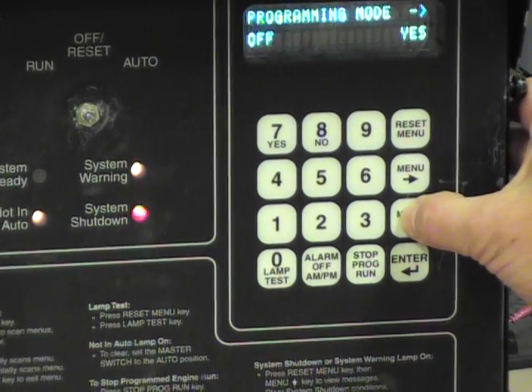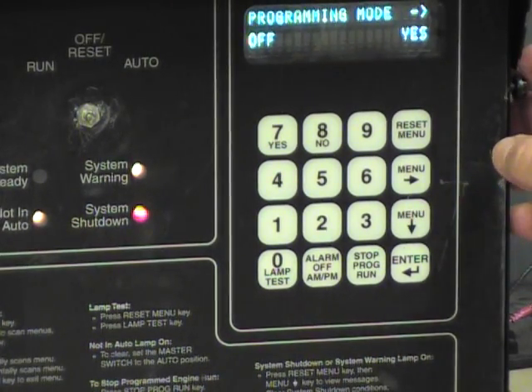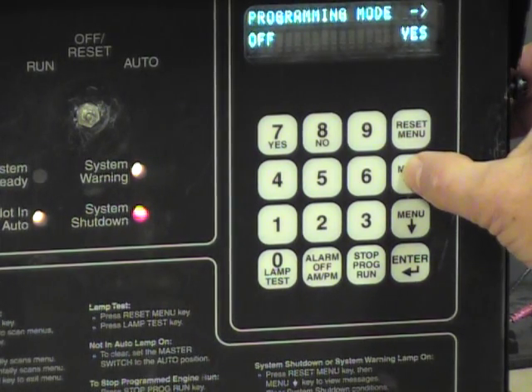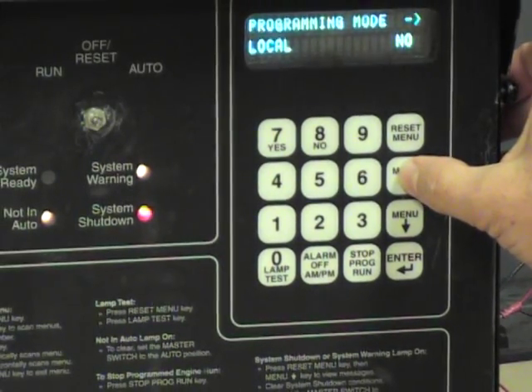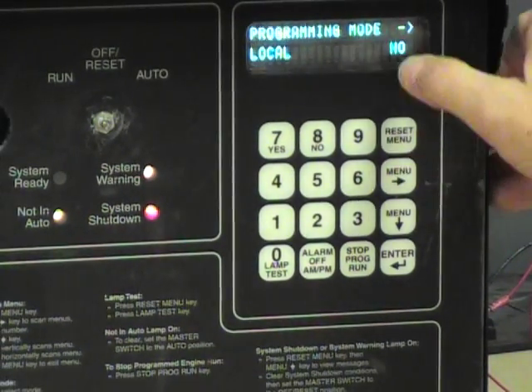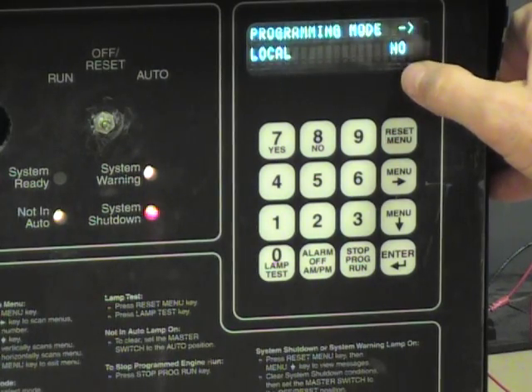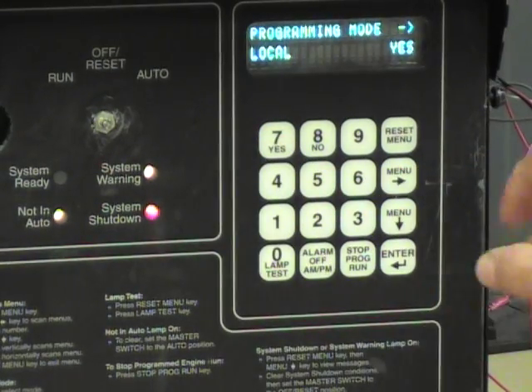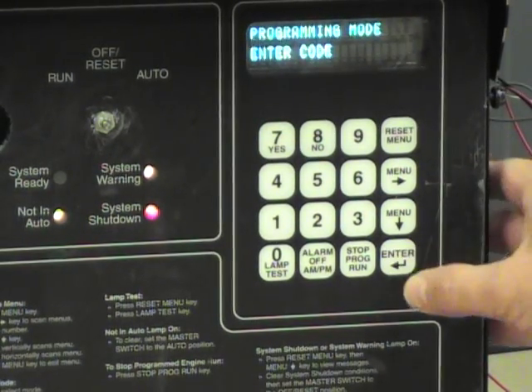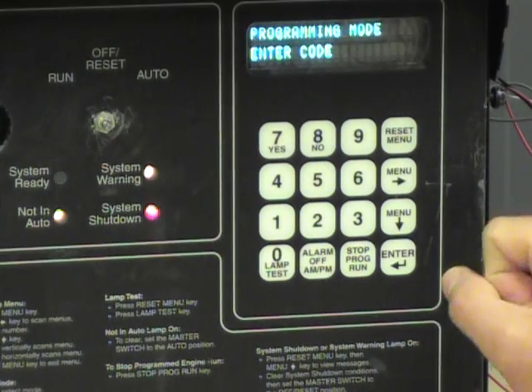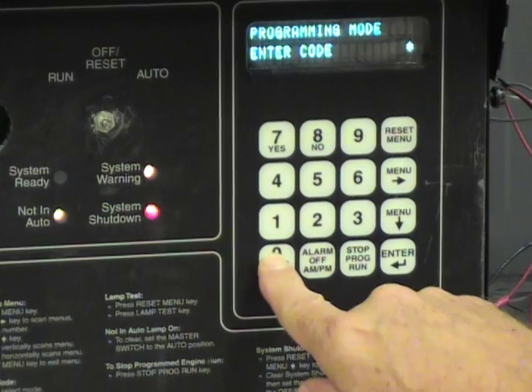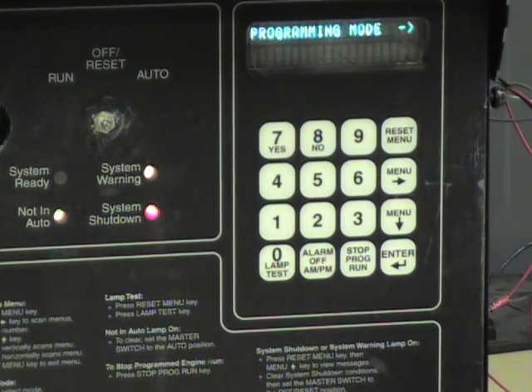Now I am going to push the down arrow key, which indicates we are in programming mode. The next thing we want to do is hit the right arrow key and go to local. Notice that right now we are in the no condition for programming mode — I am going to press yes. Now I am going to hit enter, and it is going to ask us for a password. The default password from Kohler is a simple zero. I will press zero and enter, and it says entry accepted. Now we are in programming mode.